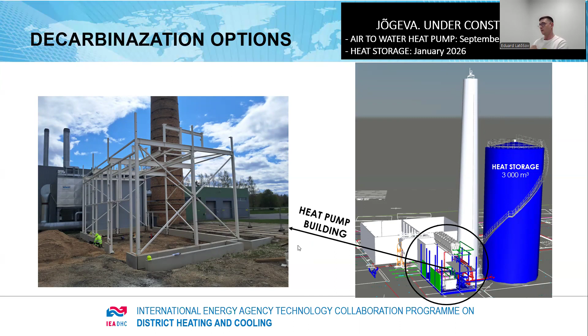There's also option number 4, which isn't probably widely discussed here: we can always add an additional biomass boiler. With a smaller biomass boiler we can cover the summer lows and cover the peaks. So the classical solution in Estonian district heating networks is to use two biomass boilers, a smaller and a larger one. This combination works quite well.